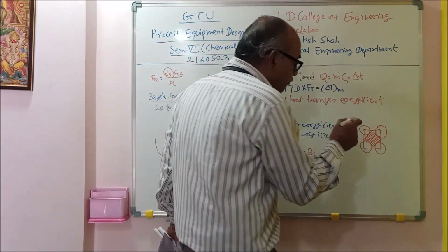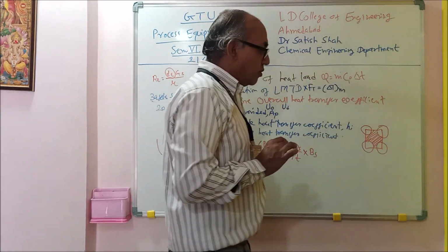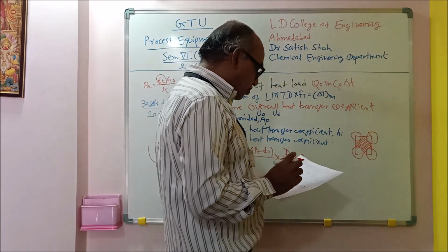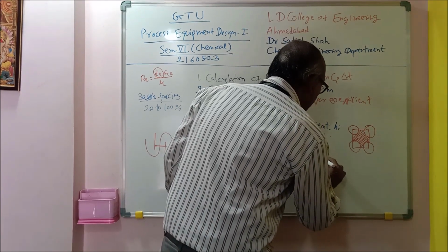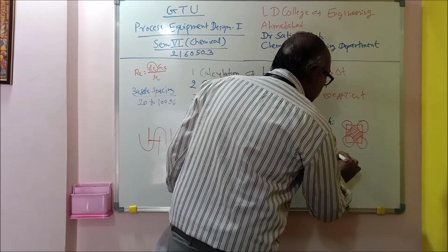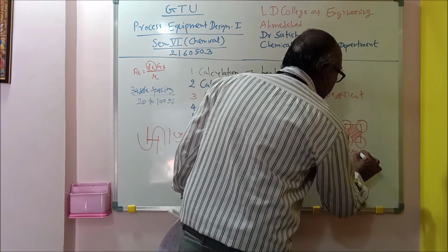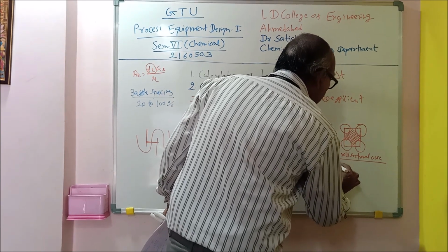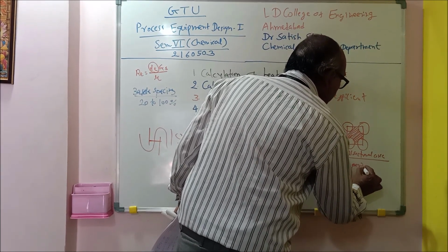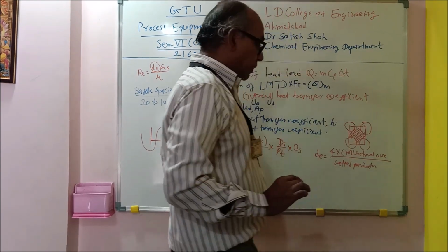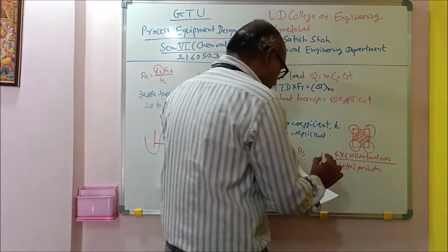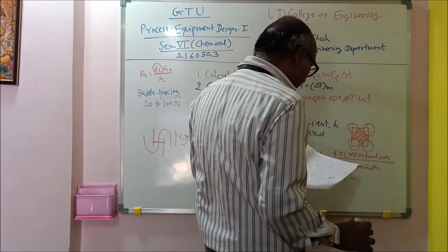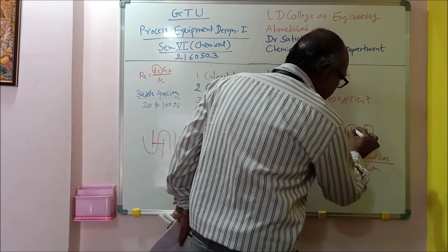The fluid is passing through this particular area which I have drawn by shaded lines. So for square pitch, you will calculate the equivalent diameter, that is equal to 4 into cross section area upon wetted perimeter. So what is that cross section area? It will be 4 into PT square minus, PT square means this is PT, the tube pitch.